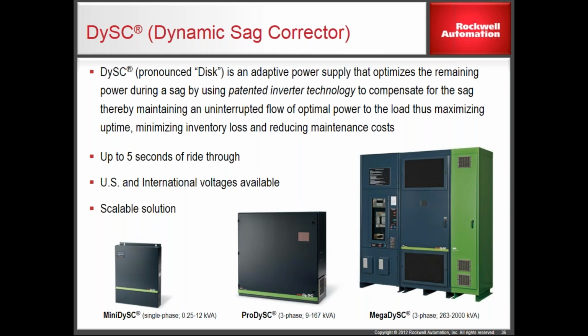Right? This cabinet over here contains extra capacitance. So the way the DySC works is it steals current to prop up voltage. But if it doesn't have enough to steal from, it adds current from capacitors. So imagine one phase goes to 0. I just double the energy out of phase 2 and prop it up. All 3 phases go to 40%. I double the current. That only gets me up to 80%. It's a 1-to-1 relationship. So now I dump energy from capacitors to push me up over 90%.